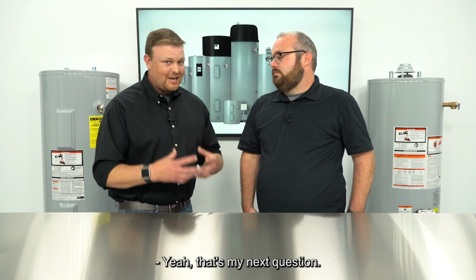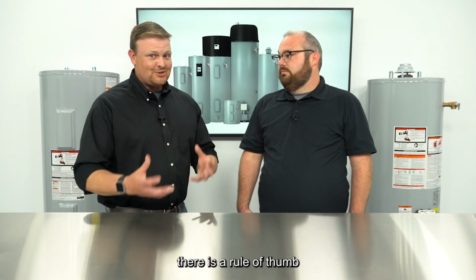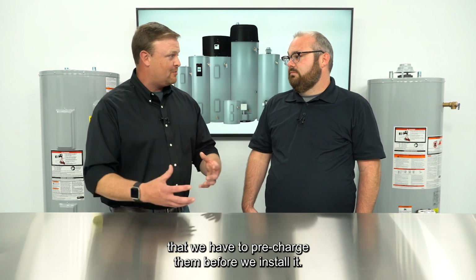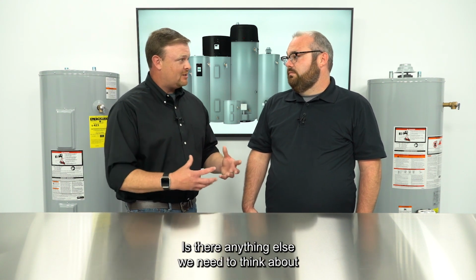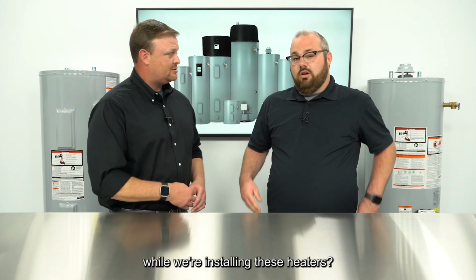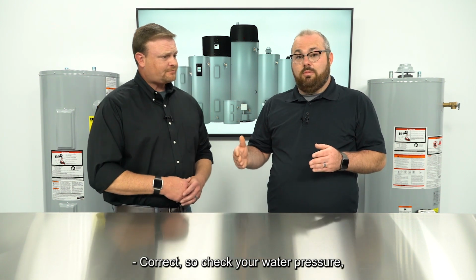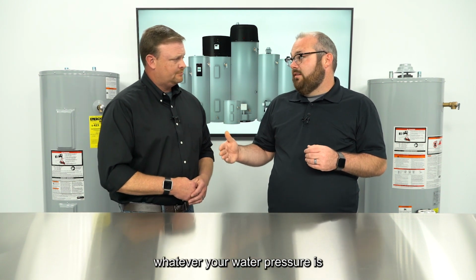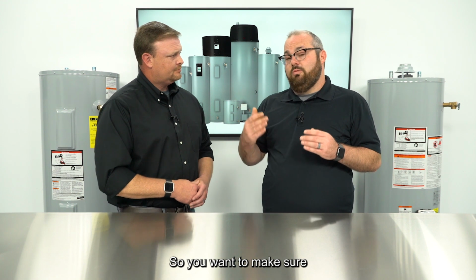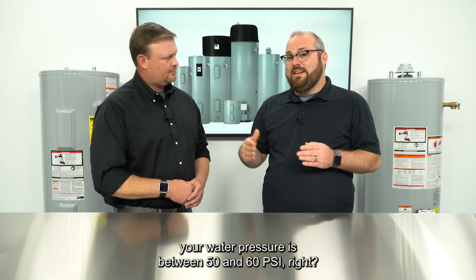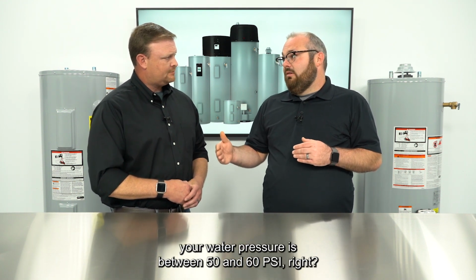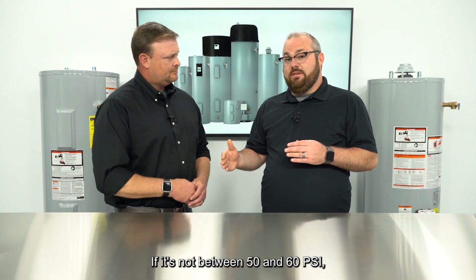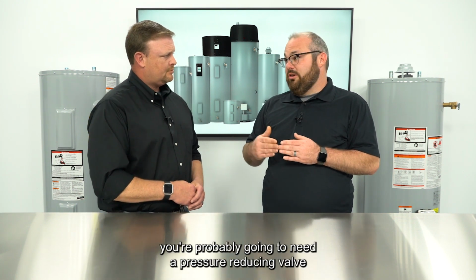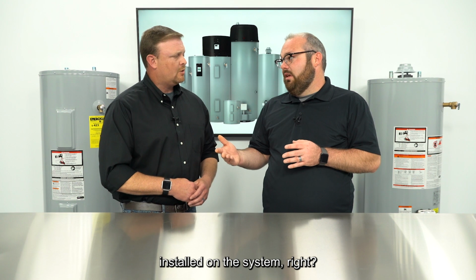That's my next question. Installing these, there is a rule of thumb that we have to pre-charge them before we install. Is there anything else we need to think about while we're installing these? Correct. Check your water pressure, whatever it is, and we need to pre-charge the tank to it. You want to make sure your water pressure is between 50 and 60 psi. If it's not, you're probably going to need a pressure reducing valve installed on the system.